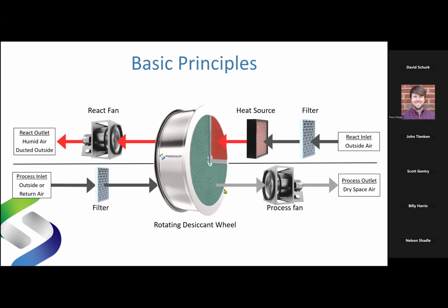But if I leave this heat in the air, I can use it to offset reheat. And it can be incredibly energy efficient, incredibly sustainable. And we do it all the time in hospital operating rooms, for example. And I'll show you a quick example of that in the slides that follow. So we've taken care of the process airstream. A lot of people look at the heat coming off the wheel. They don't understand that it's just a part of psychrometrics. They go, well, that is weird. That's not how we do it in traditional systems. Yes, it is. And it can't be energy efficient. And yes, it can. So we'll come back to all that.